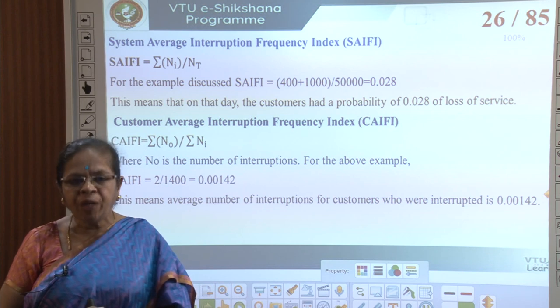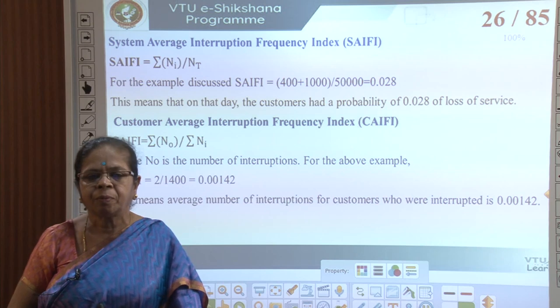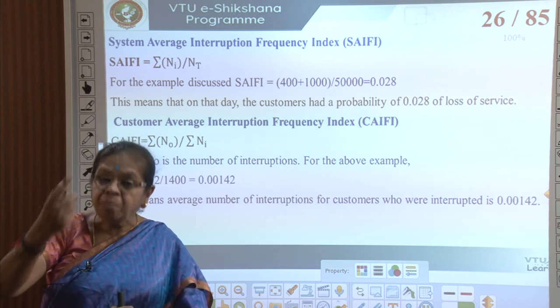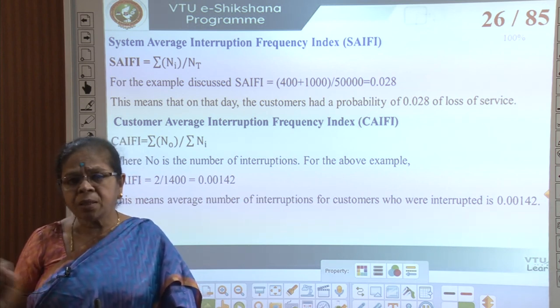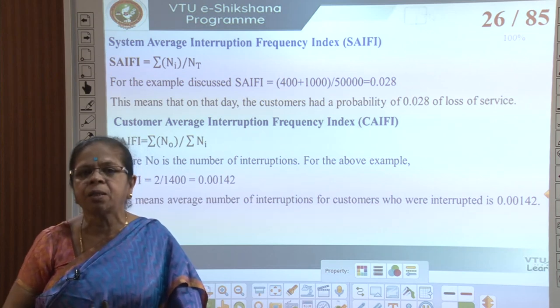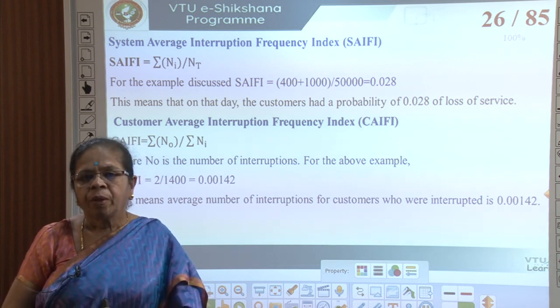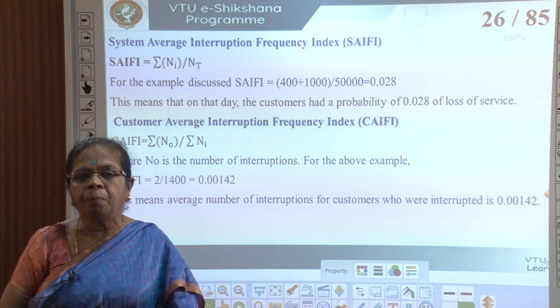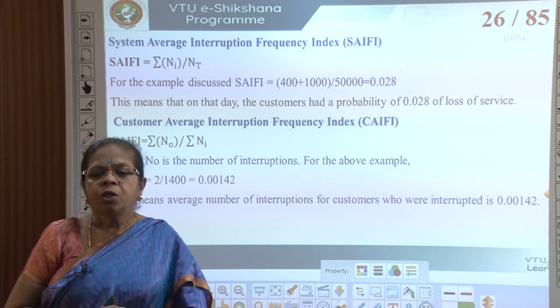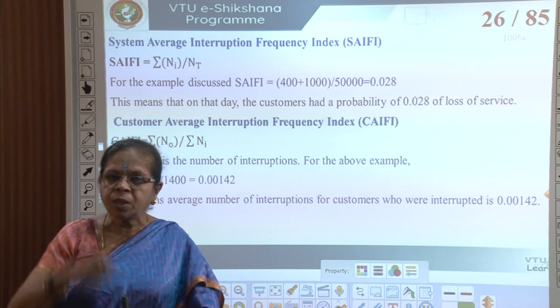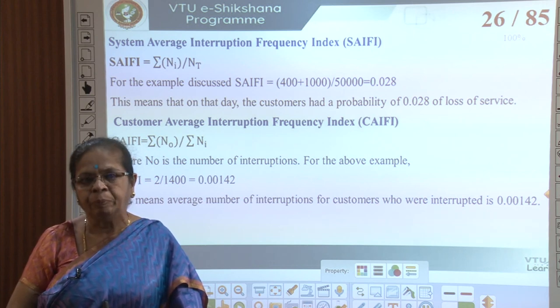The other index is CAIFI — Customer Average Interruption Frequency Index — which tells you how many times there was an interruption. N0 is the number of interruptions; this does not consider how many customers were affected, just how many interruptions occurred. There were 2 interruptions affecting totally 1400 customers, so that gives you 0.00142. This means the average number of interruptions per customer who was affected is 0.00142 in a day.